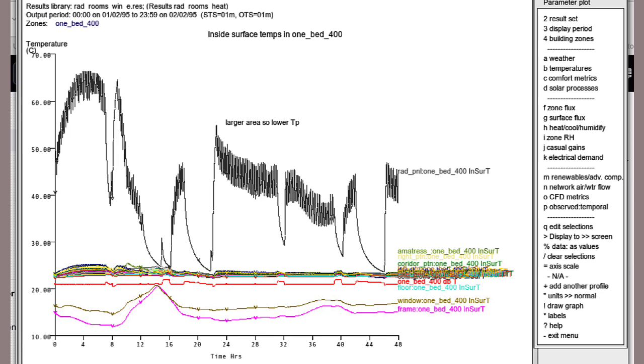All the cluster of lines just above the red line, that's all the other surface temperatures in the room, except for the panel heater. And that's shown in black. That kicks on and ratchets a bit. Picking up, we reach set point, drops down, comes back up again. And so it responds sufficiently in temperature over time to maintain quite a tight dry bulb temperature inside the room.